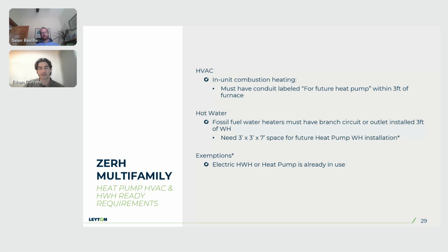The final electrification ready requirement is based around heat pump HVAC systems and heat pump hot water heaters. If you are using combustion heating or a combustion hot water heater, you must install a conduit, branch circuit, or outlet within 3 feet of the equipment that indicates readiness for future installation of a heat pump HVAC system or heat pump hot water heater system. There are also exemptions here, if you are already using electric hot water heater systems or heat pump HVAC systems.